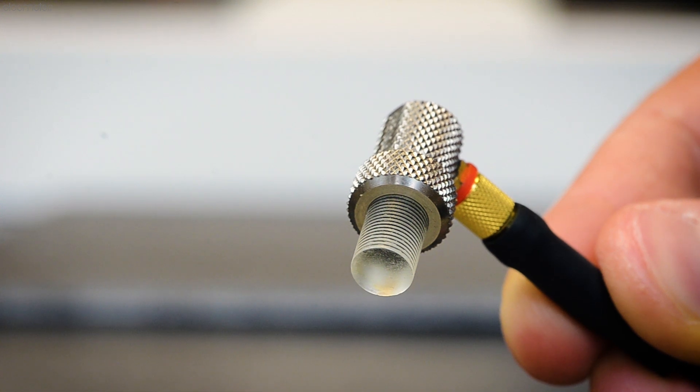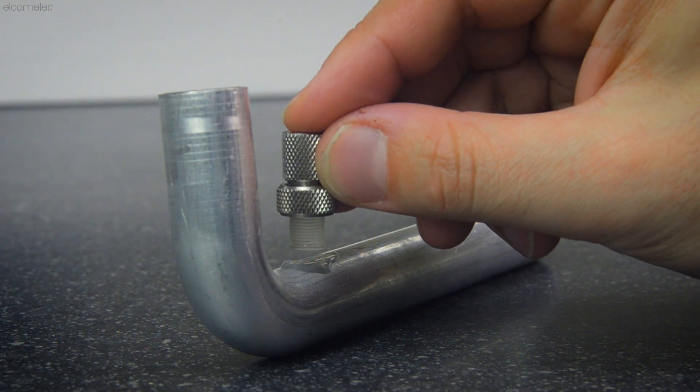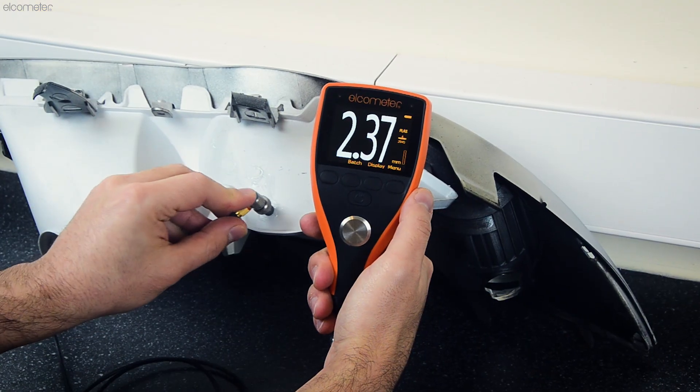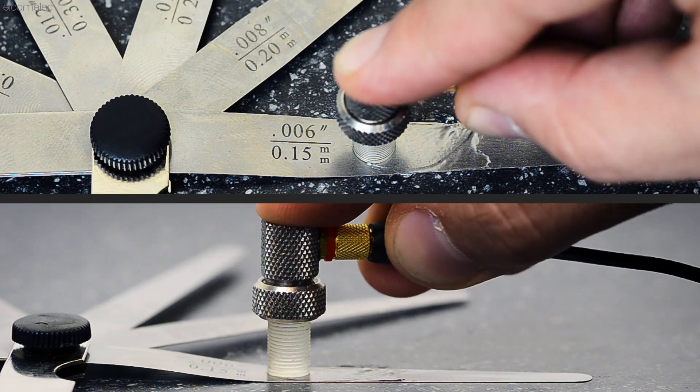The Elcometer PTG range uses single element transducers to provide precise, accurate material thickness measurements to one hundredth of a millimeter or one thousandth of an inch of thin, uncoated materials such as steel, titanium, and plastic, from as little as 0.15 millimeters thick.